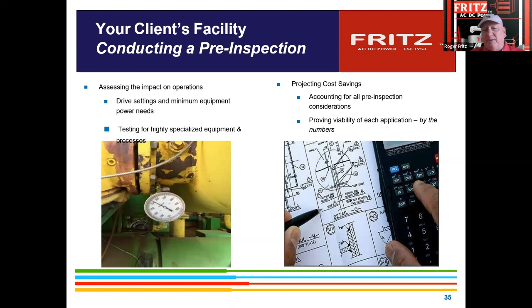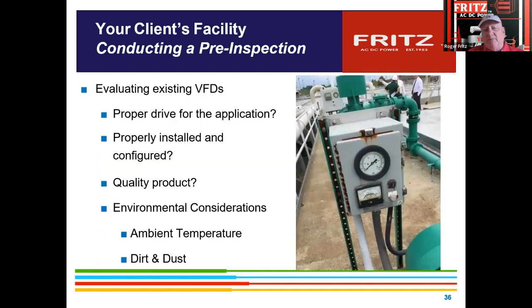Get that pre-evaluation. And then there are sometimes a lot of extra incentives where you can put in what they call measurement and verification. The drive controls have kilowatt-hour meters, most of them built in, so you can data log how much actual savings you're getting out of that machine and bring it back to your BMS system through various networks. They are compatible.